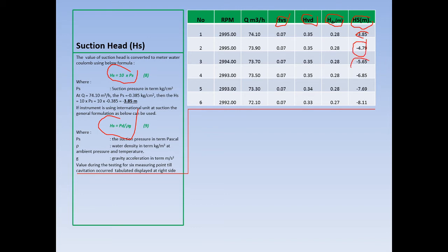Minus means that the suction head is lower than atmospheric pressure. Because every pump being tested is based on the pressure difference to the atmosphere, not absolute pressure.